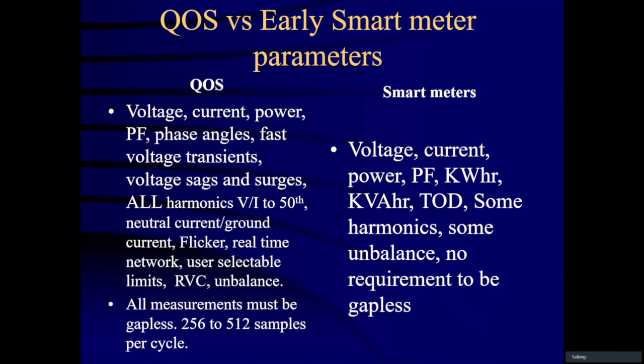RVC is a new term, it's only been around a couple of years, is rapid voltage change, and it's a different version of a sag, and then unbalance or imbalance. As the IEC standard requires, all measurements must be gapless, which means you continuously digitize the waveform. And today the state of the art is probably 1024 samples per cycle, but it generates too much data, so the standard used is either 256 or 512 samples per cycle. You remember the RPM, we did 128 samples per cycle. So 256 times 4 and then 512. So that's a lot of data being generated, and that's 16-bit A to D.